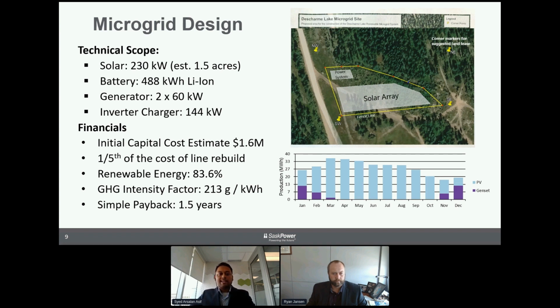Once this microgrid is set up based on the sizing of these components, 80% of the energy is expected to come from the renewable source, the solar, and less than 20% from diesel during those days when there's not enough sunlight - the winter days are very long, there's too much darkness. That bar chart on the right shows the dark section as energy provided by the diesel genset, a small fraction of the year, and the light blue bars provided by solar energy. This system will perform at an emission intensity of about 213 grams per kilowatt hour.